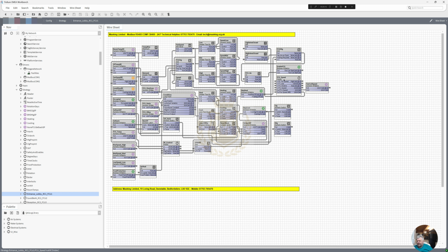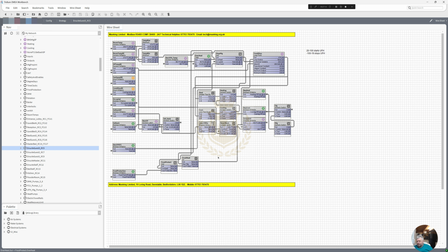We've got a speed select folder there. So we've got our loop point now. We're doing minus 100 to plus 100 here. So minus 100 is for cooling, plus 100 is for the heating. We've got a set point of 20.5. The control variable is 25.5. Hence, that's why we're showing the minus. So we're not in heating mode. We are in cooling mode. True. And require cooling. True. And output set point is 20.5. Right. It will be the same for all these. With fan coils, this won't be the same, because this is for underfloor, I believe.